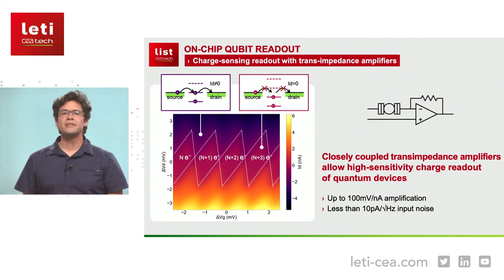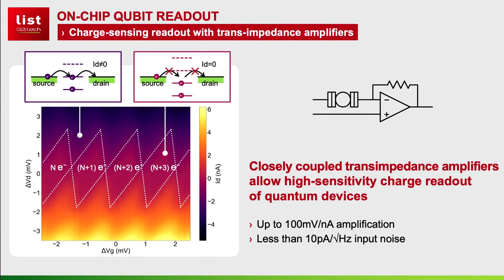As regards measurement, we have been working on closely coupled transimpedance amplifiers for high sensitivity charge readout of quantum devices. Based on a splitting of the quantum energy levels and fine-tuning of the Fermi level, it is possible to leverage blockades in the electron flow for current sensing of the quantum state, amplified using TIAs with up to 100 millivolts per nanoampere, and less than 10 picoampere per square root of Hertz input noise. These works were presented at the 2020 International Solid State Circuits Conference.